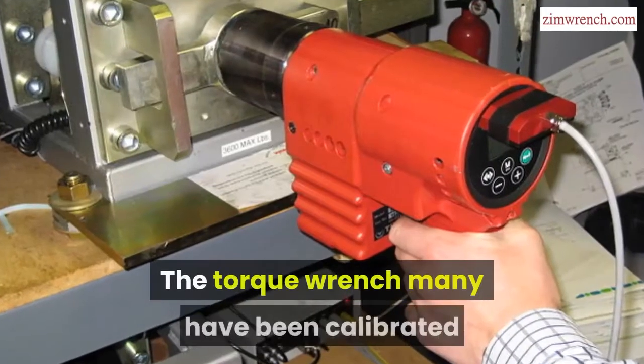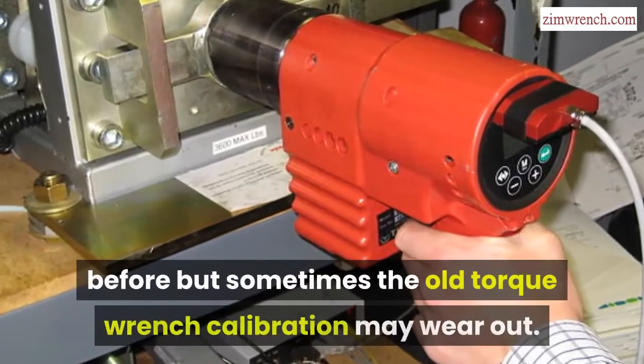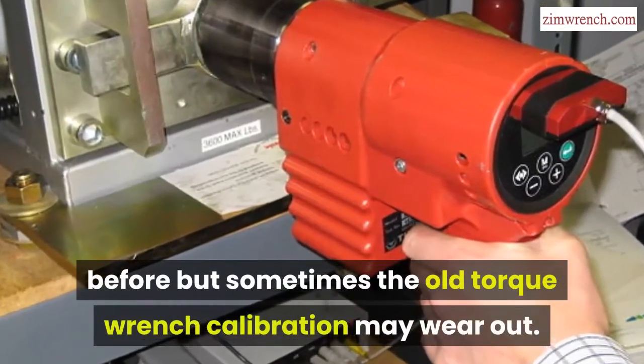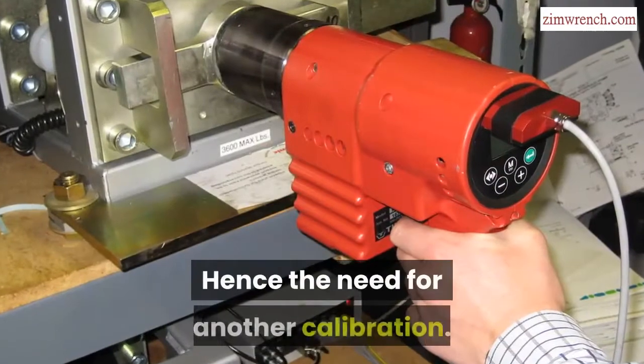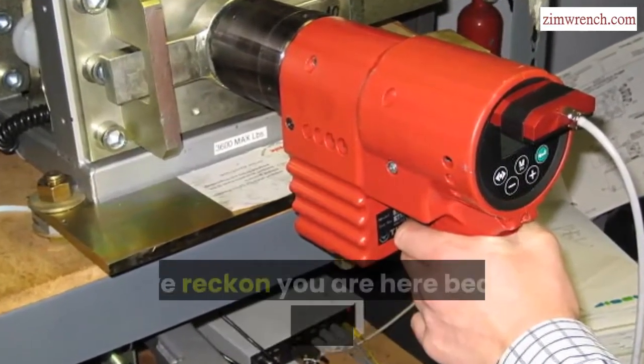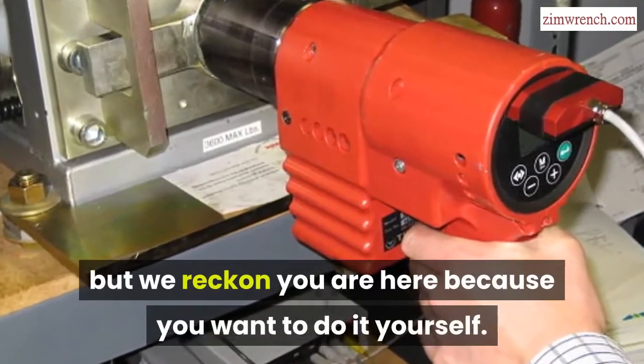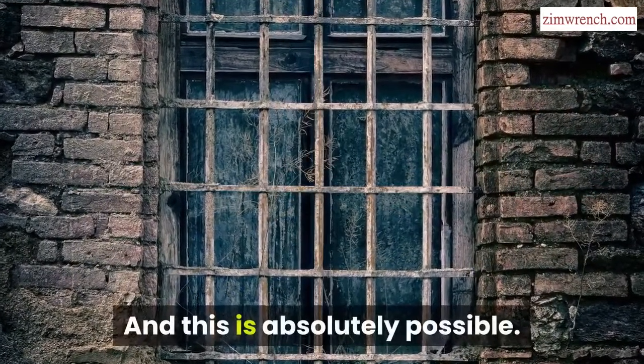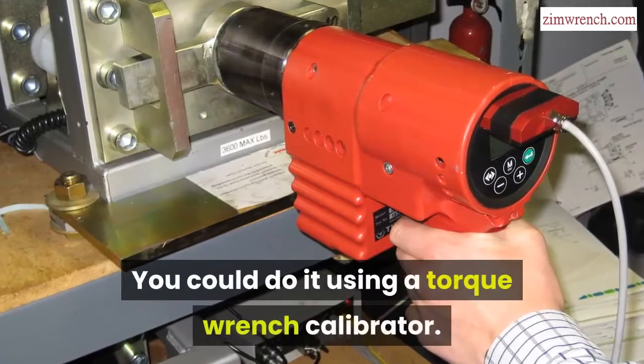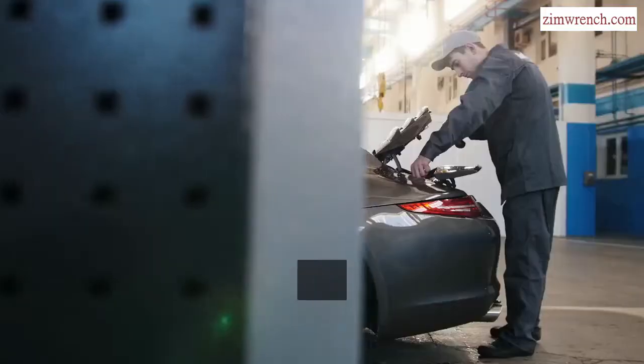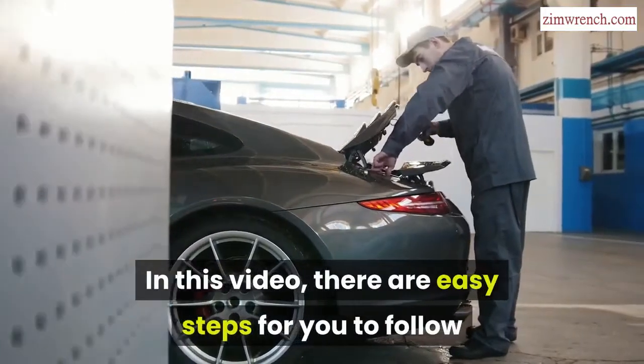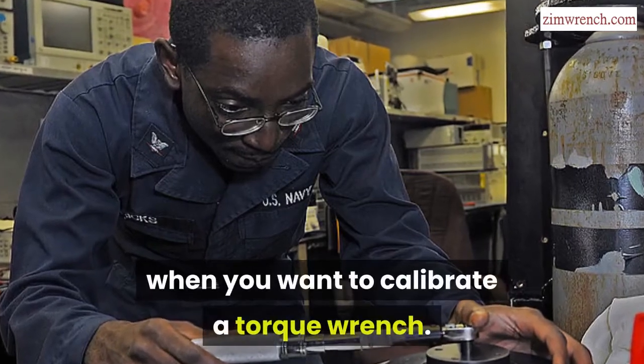The torque wrench may have been calibrated before, but sometimes the old torque wrench calibration may wear out. Hence the need for another calibration. A pro calibrator can do the calibration, but we reckon you are here because you want to do it yourself. And this is absolutely possible. You could do it using a torque wrench calibrator. In this video, there are easy steps for you to follow when you want to calibrate a torque wrench.